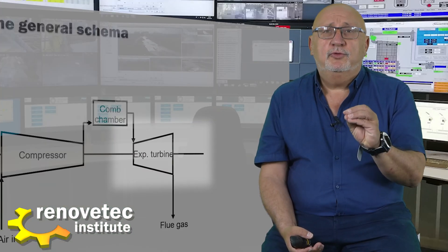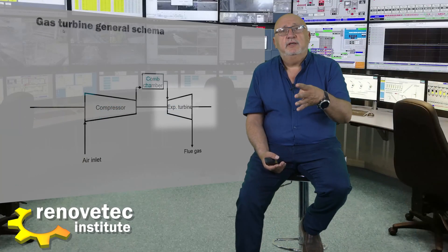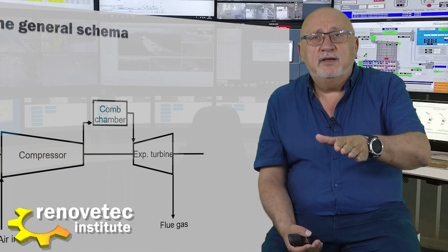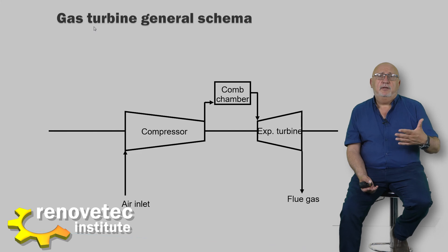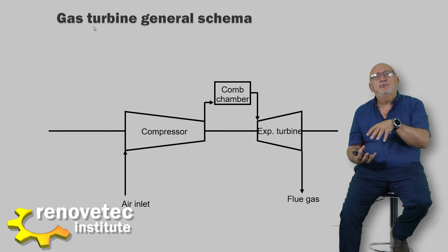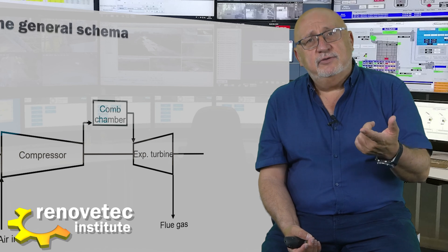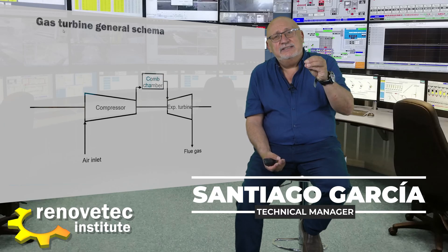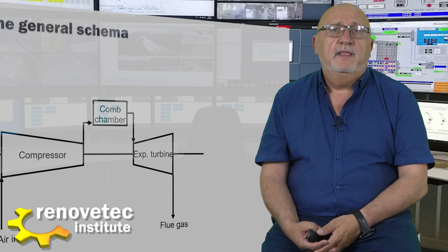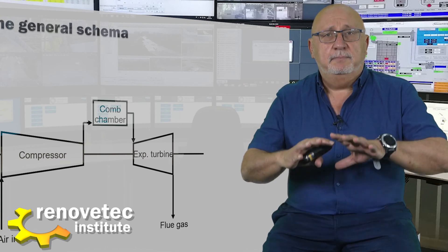The inlet pressure could be, as mentioned before, between 8 and 30 bar — most normally around 10, 12, or 15 bar. In the expansion turbine, we transform the potential energy contained in the heated and pressurized air into kinetic energy. This transformation is made in two steps: first, it is necessary to accelerate the air by changing pressure into speed, and second, to transfer the kinetic energy of the air into kinetic energy in the blades. The expansion turbine is the third main element of the gas turbine body.